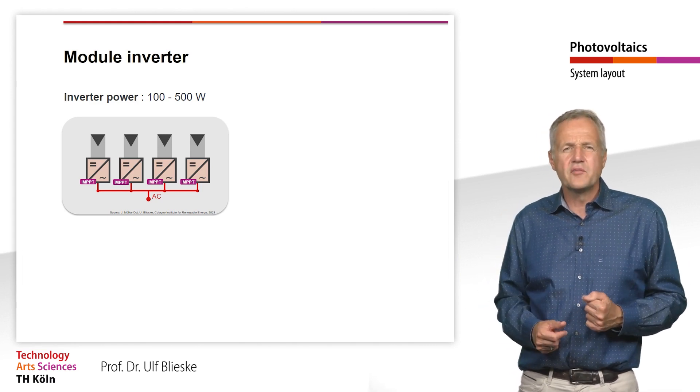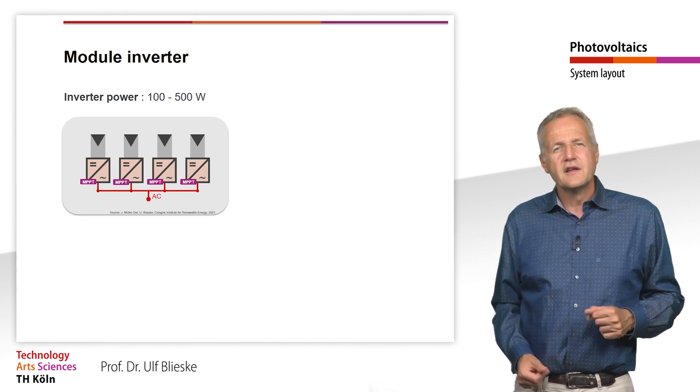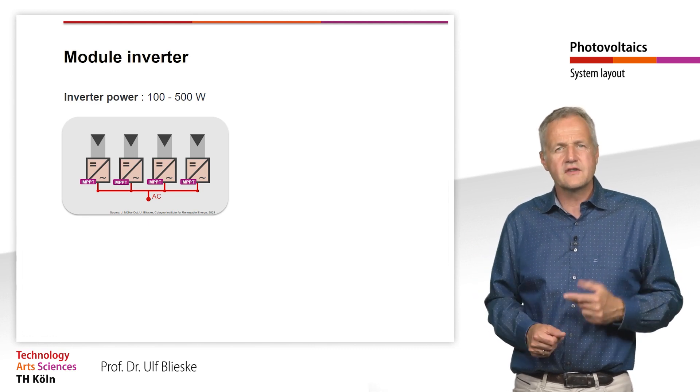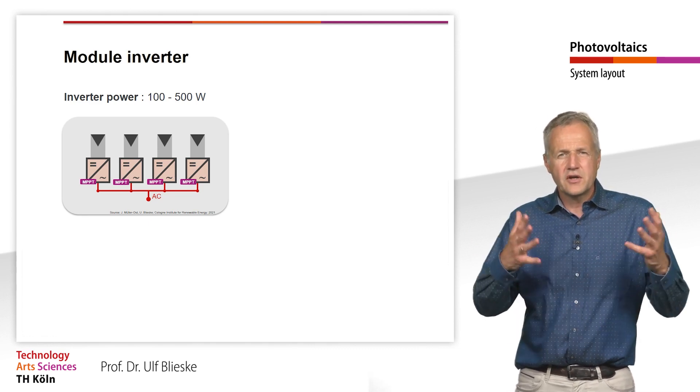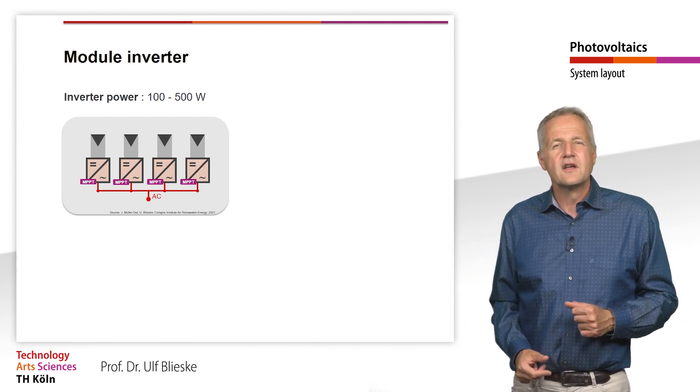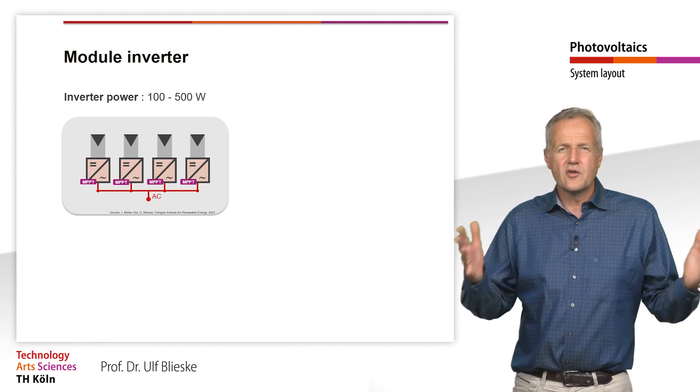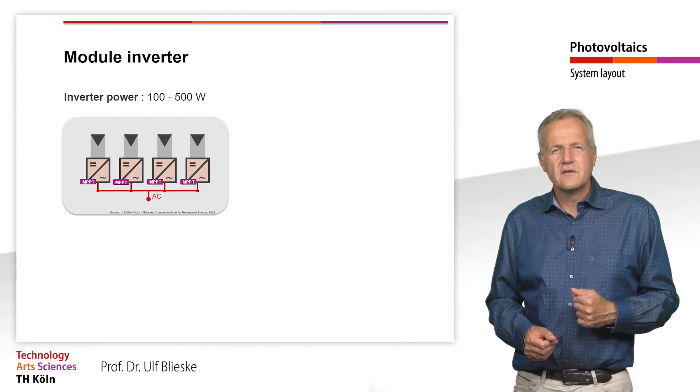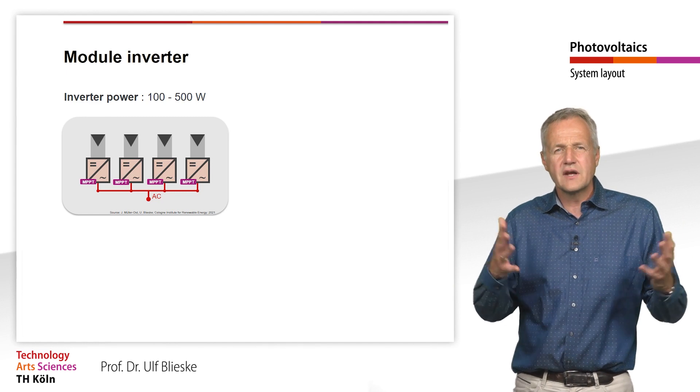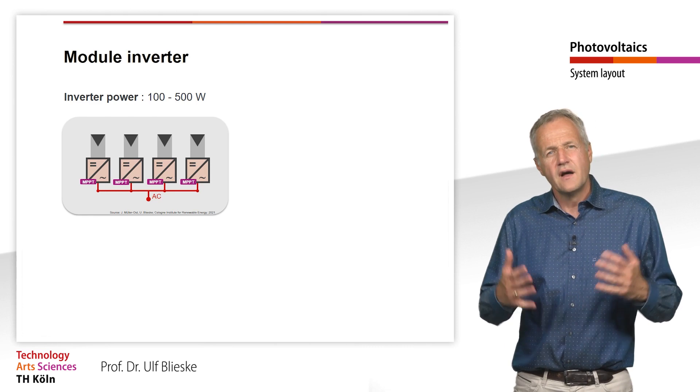Another advantage of the module inverters comes from the fact that they are mounted directly on the back of the module. This eliminates the need for DC wiring to the modules, which in turn reduces system costs. Last but not least, a PV system with module inverters can be expanded as needed. So, if more modules are to be installed after a few years, there is no problem with module inverters. This would not be so easy with systems using string inverters, as for string inverters, there is a maximum number of modules due to its maximum input voltage.